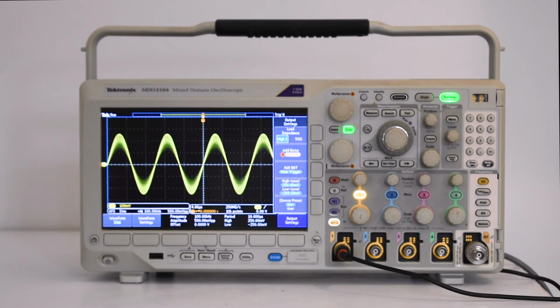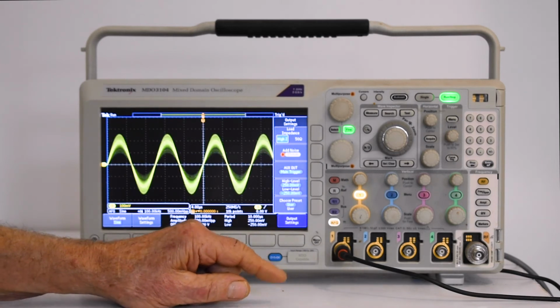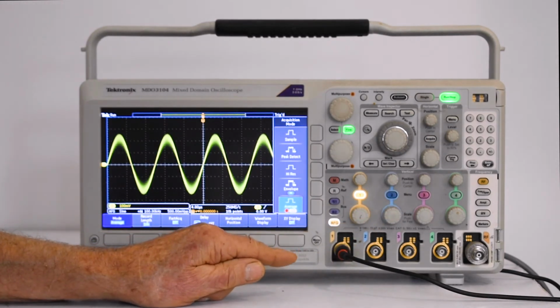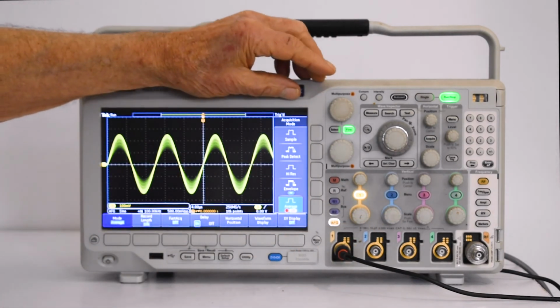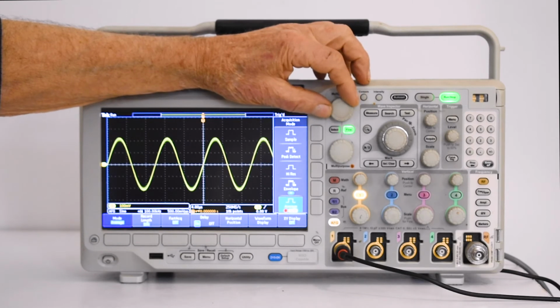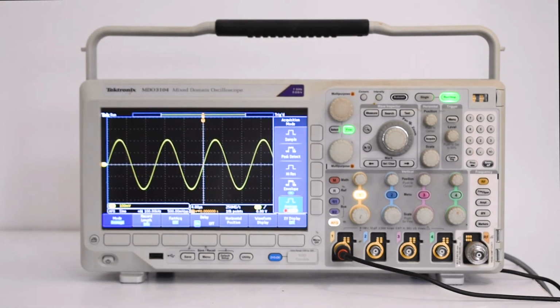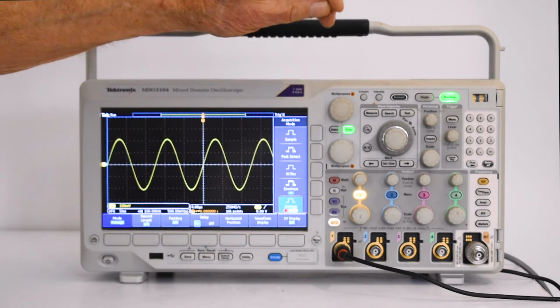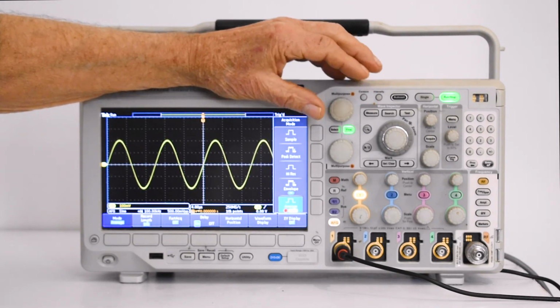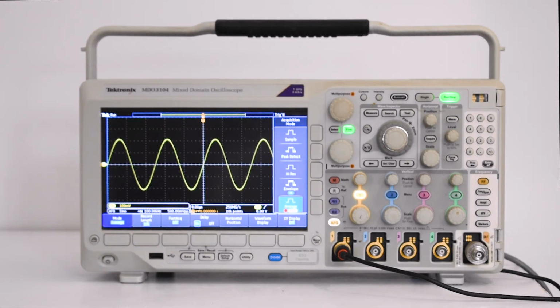Now, back to waveform averaging, we'll turn the multipurpose knob A in order to average increasing numbers of the waveform. When we get to 256, the waveform is much freer of noise and triggering has been restored. Notice that the trace appears to throb a slight amount due to averaging. Turning the number of waveforms that are averaged up to 512, notice how clean the trace appears. It is even better than before noise was added.